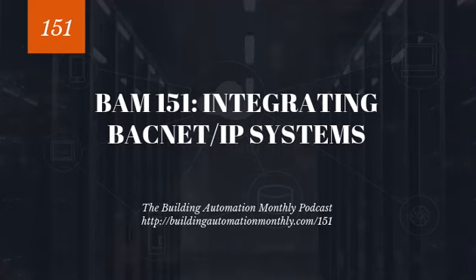So because we're writing at maybe level 15 on the priority array instead of level 8, now that lighting system, as soon as it gets some sort of command from its lighting schedule, it overrides whatever the BAS is doing. And you all have been there. You all have done this. You've integrated to a Lutron system via BACnet IP, and you've had them have a schedule in their Lutron system, and it overrides whatever you're doing in the BAS. And it's a freaking nightmare to troubleshoot. Well, we avoid that by doing our data flow map.